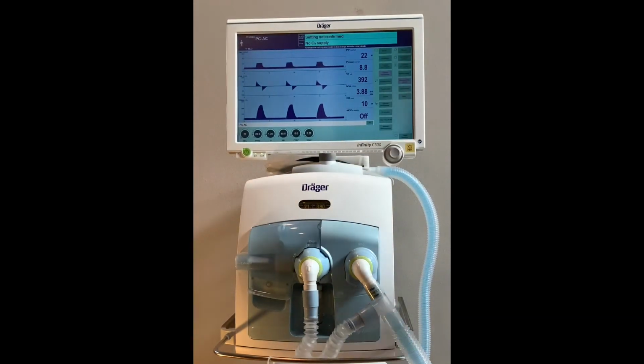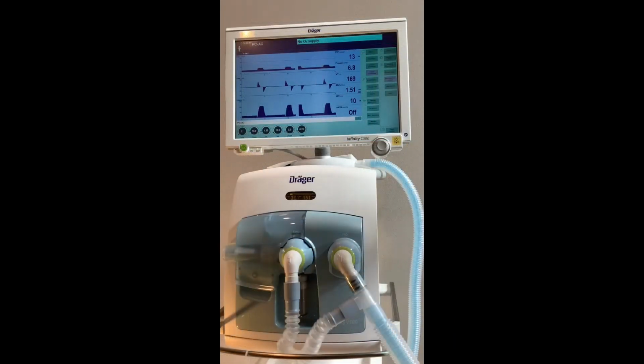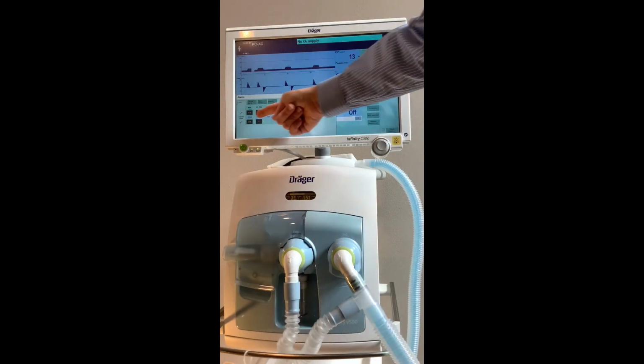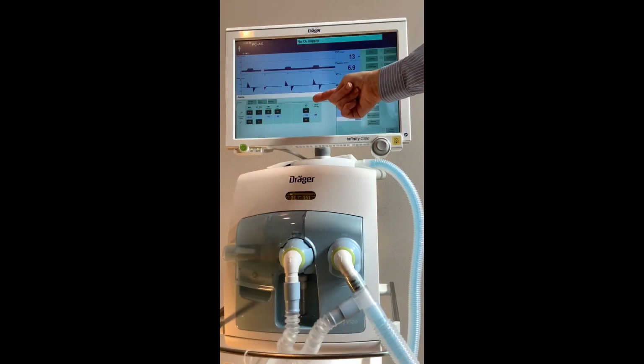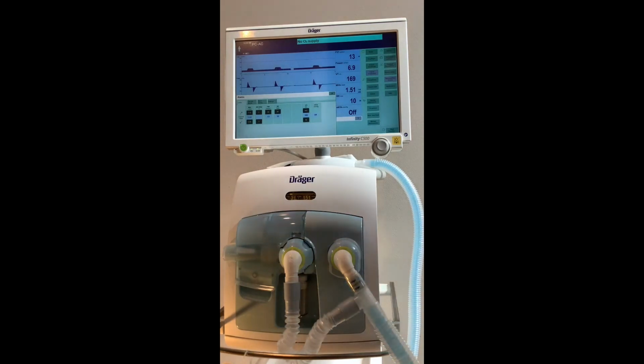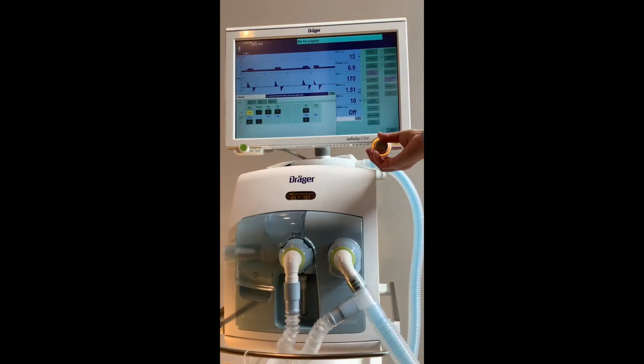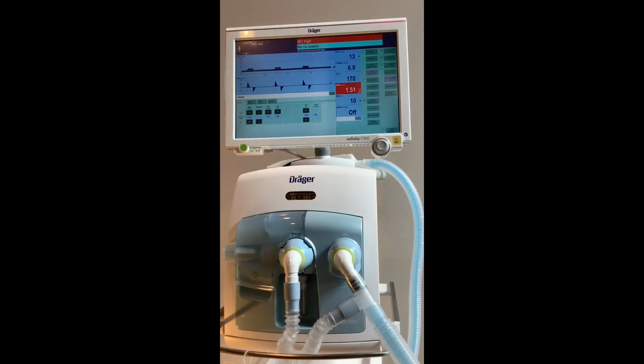To set the alarms, touch the Alarms tab in the upper right-hand corner of the screen. Here you will find all the active alarms for the mode of ventilation. You'll see your patient values in the center, high alarms on the top, low alarms on the bottom. To make changes, use the same touch, turn, confirm procedure. Touch the button, turn with the rotary knob to set the desired value, confirm by pressing the button.